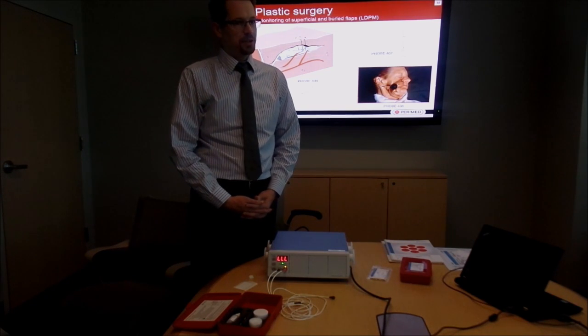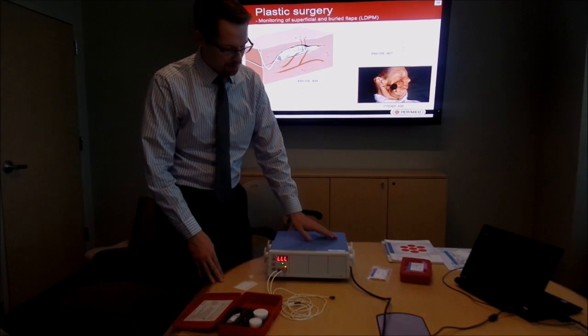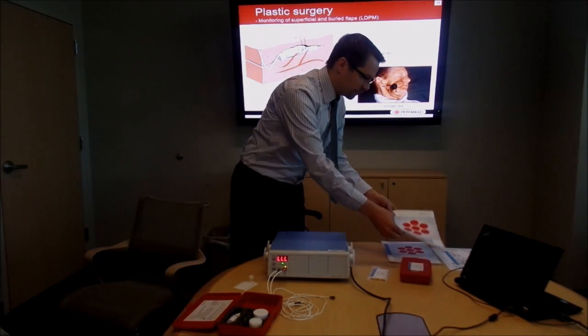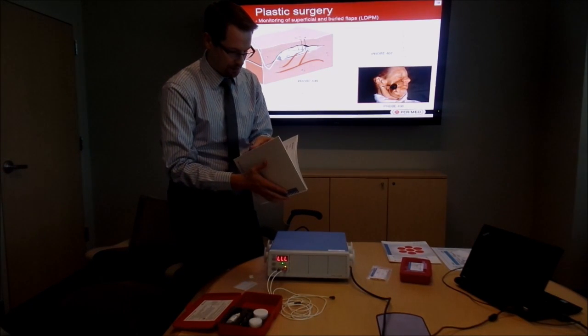That is pretty much it as far as I can think of right now. And then just processing of the actual probe, once we do have it calibrated, it would be STERRAD. Is there a certain temperature? Yes, and the manual will state this, and I can probably find the page that is on.